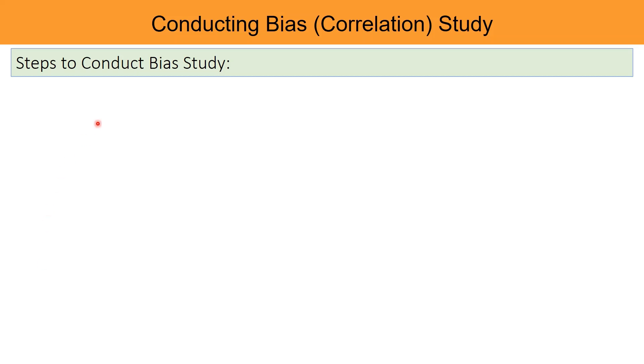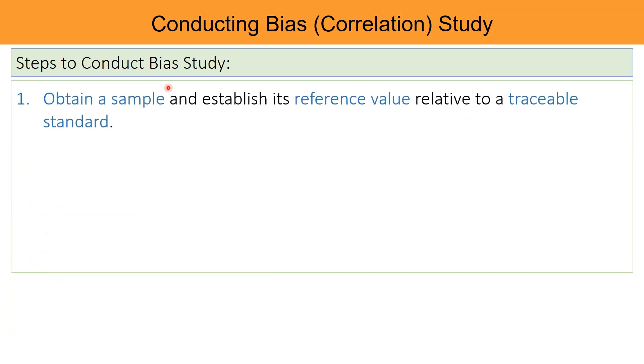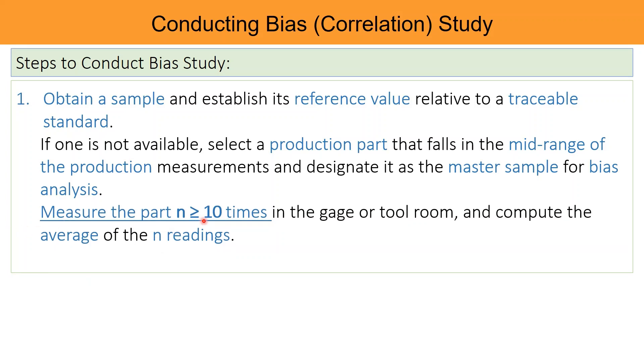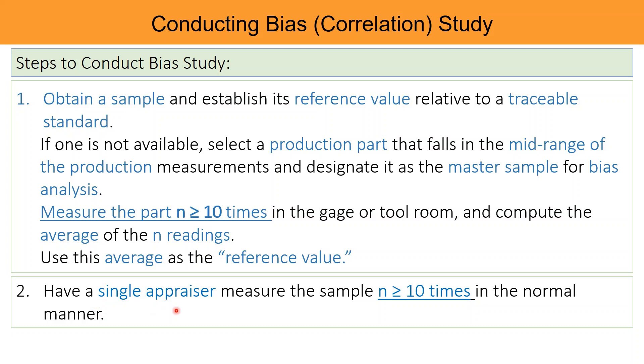Steps to conduct a bias study: Obtain a sample and establish its reference value relative to a traceable standard. If one is not available, select a production part that falls in the mid-range of production measurements and designate it as the master sample for bias analysis. Measure the part more than 10 times in the gauge or tool room and compute the average of the n readings. Use this average value as the reference value. Then have a single appraiser measure the sample more than 10 times in the normal manner.